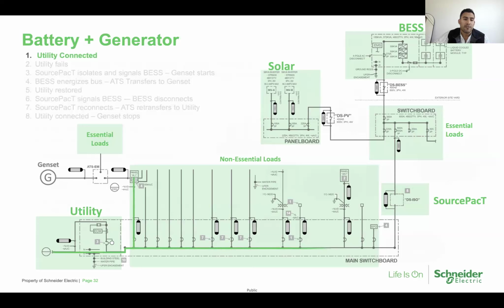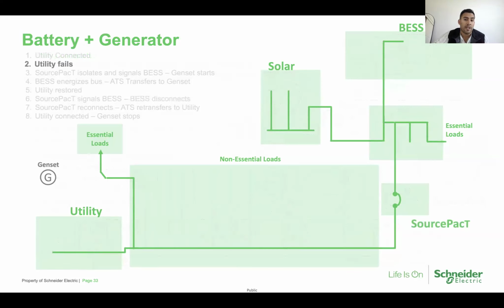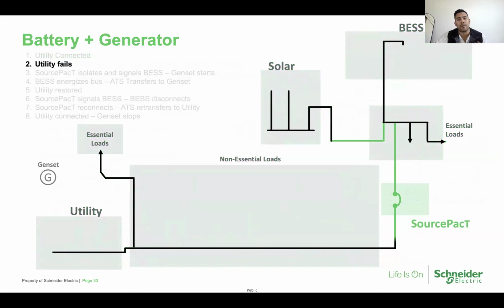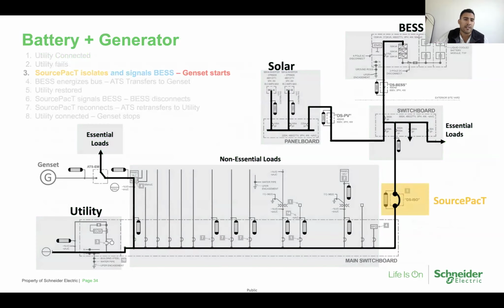So this is the same single line diagram. The only difference here is we have an automatic transfer switch, and this is the same design. I'm showing this diagram here to highlight the benefits of having an existing generator and battery energy storage system. Both the systems operate independently. So what I mean by that is when we lose power, the ATS will sense that power has been lost, so will the SourcePacT controller. Once we detect that utility's been lost, SourcePacT will isolate.